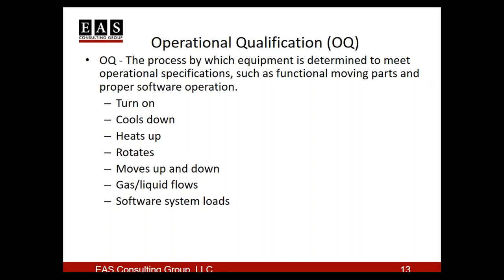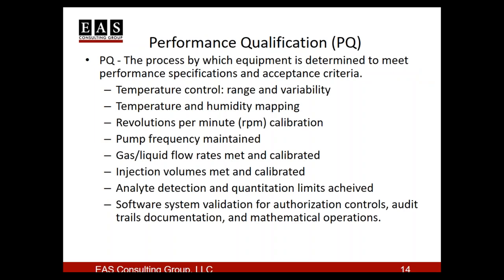For a performance qualification, now we're going to get more serious about what the specifications are of that piece of equipment. So not only did it get cold, but what temperature range is it meeting, and how variable is that? We may need to temperature and humidity map this. If this is a stability chamber, an incubator, or even a larger oven, you may need to put data loggers throughout the equipment and make sure it meets those requirements throughout the entire unit.